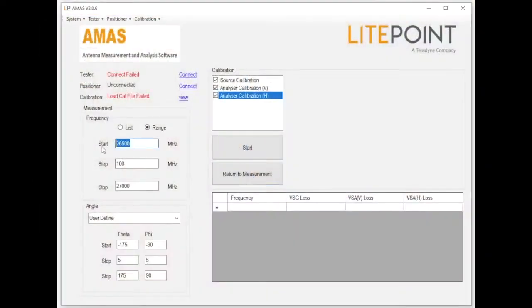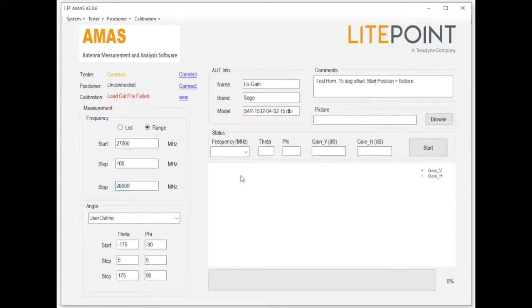On this screen, we define the frequencies and RF paths that will be used for calibration of the chamber path losses. To perform these measurements, either the IQgig 5G or an external RF power meter can be used. Here we set up the parameters to perform RF measurements of our patch antenna. We define the frequencies which will be used, and we define the three-dimensional coordinates that will be used. And then we start the measurement.